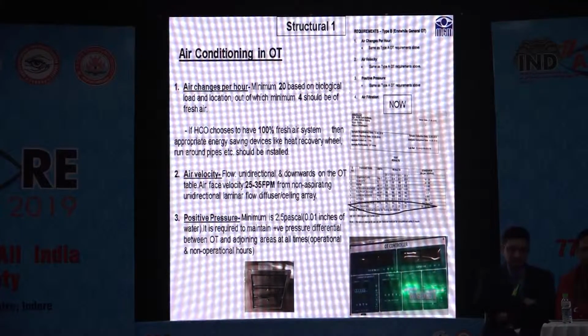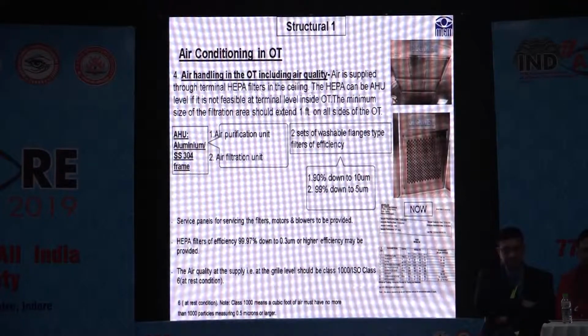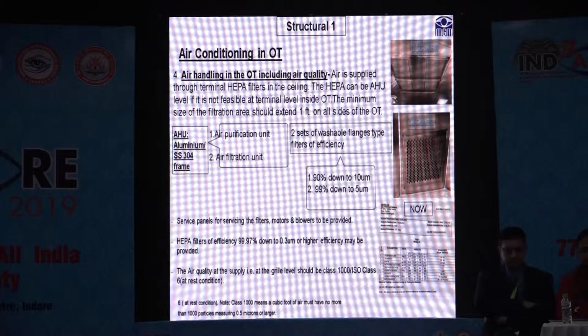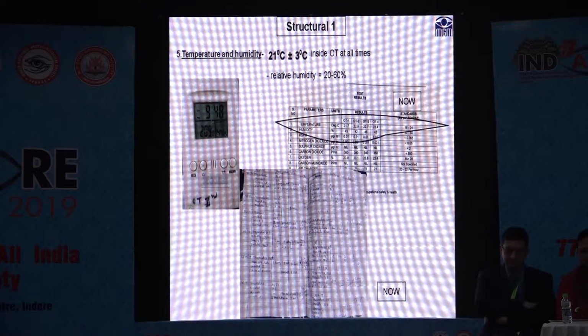HEPA filters were already discussed, but I would like to emphasize that the air quality at the supply, that is at the grill level, should be Class 1000, ISO Class 6, at rest condition. The temperature and humidity have to be maintained as per the given standards. This is a recent 2018 standard. We have installed all the devices to measure whether these standards are being maintained or not.